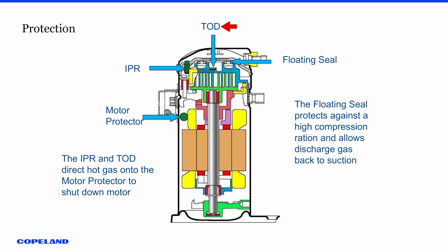And it trips, the bimetal flexes, and it usually opens a switch. Well, in this case, when it flexes, the refrigerant flows through it, okay? So there's no switches or anything, it just flows the refrigerant through it. And then the IPR goes off of pressure differential from the high side to the low side, okay? And both of those, the TOD and the IPR, will direct that high pressure right on top of that motor protector. So the motor protector will go off on temperature or higher current.